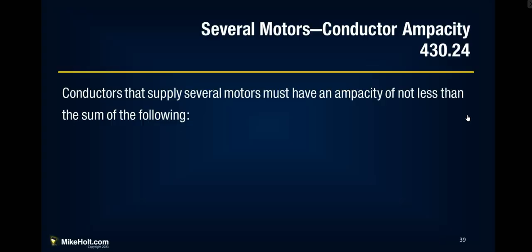So, moving on. Several motors, conductor ampacity. Conductors that supply several motors must have an ampacity of not less than the sum of the following. And that is 430.24. You look in your code book under 430.24. First of all, under 430.22, which was mentioned earlier, single motor. Conductors that supply a single motor used in a continuous duty application shall have an ampacity of not less than 125%. Have it in your head that you have to calculate that ampacity from the tables in the NEC times 125%. Keep in mind, and the slide will come up here soon enough, we are not talking about overloads. You calculate the overcurrent protection and conductor sizing for a motor based on the FLC from the tables. You size overload protection for a motor from the nameplate rating.